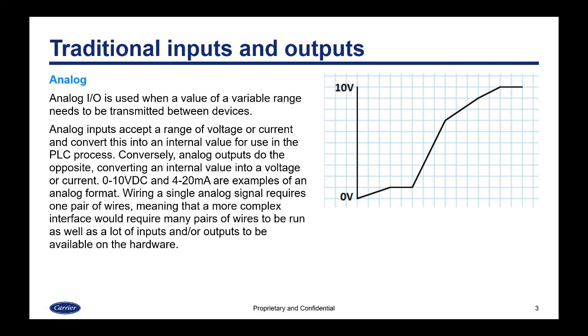With traditional inputs and outputs, we'll start with analog. Analog I/O is used when a value of a variable range needs to be transmitted between devices. Analog inputs can accept a range of voltage or current and convert this into an internal value for use in the PLC process. Conversely, analog outputs do the opposite — they convert an internal value into a voltage or current. 0 to 10 volt DC and 4 to 20 milliamp are examples of analog that most of you are familiar with.